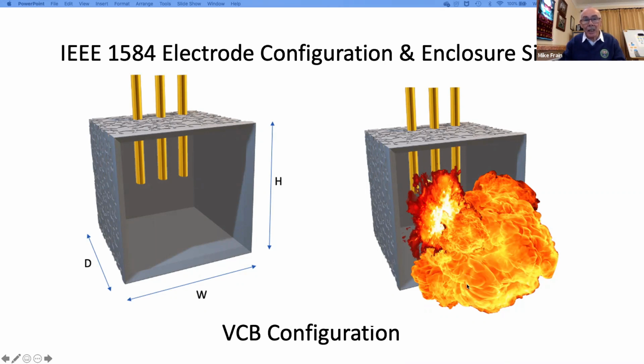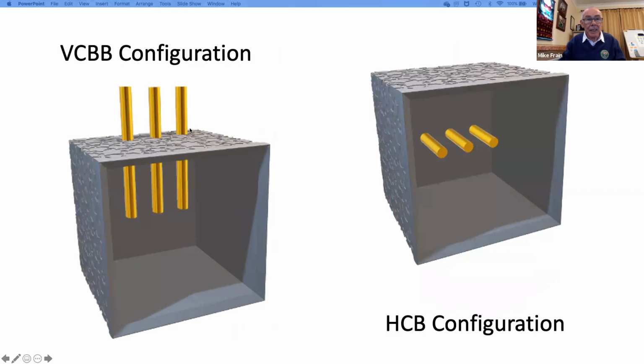So you can see what the arc looks like, that it's forced downwards and out towards the worker. Next one is VCBB configuration. I'm sorry, but I've put the wrong slide up there, so you'll have to take it from me on this one. I'm really sorry. But on the left-hand side, that should have shown a barrier across the bottom of those particular conductors. And VCBB stands for vertical conductors in a box, but terminated into a barrier. So you'll have to use your imagination to see a barrier across there. What happens is when the arc hits the barrier, then the plasma cloud is driven out towards the worker.